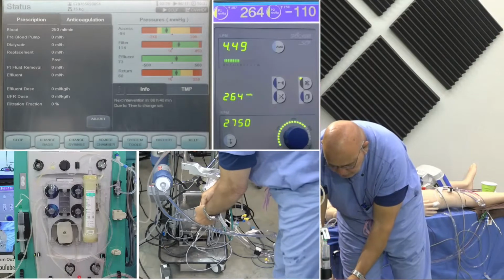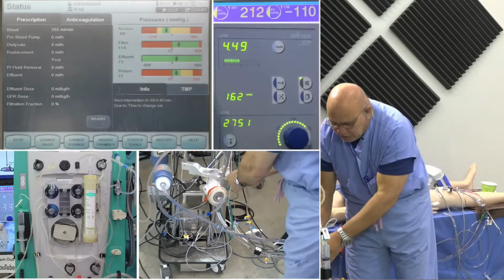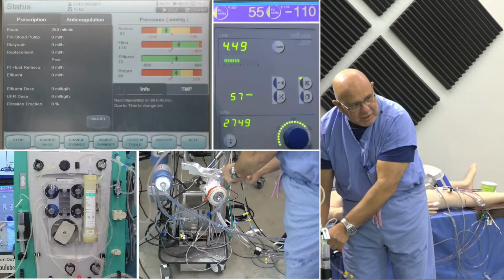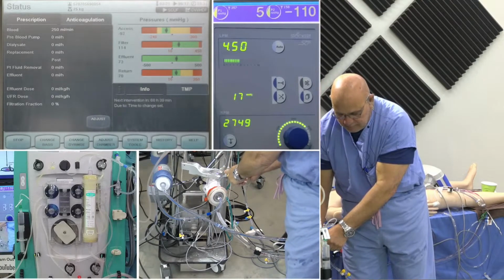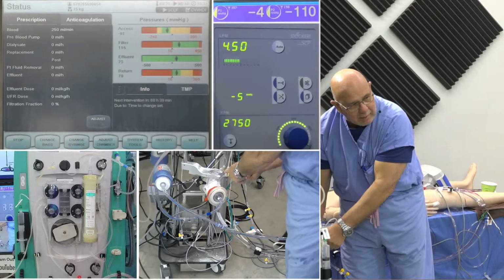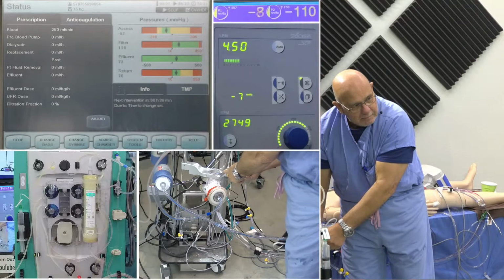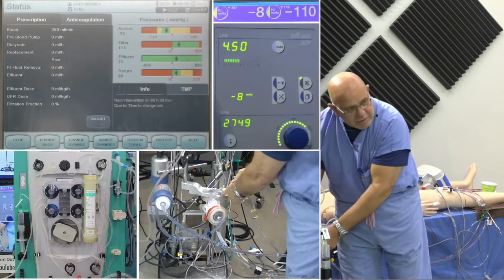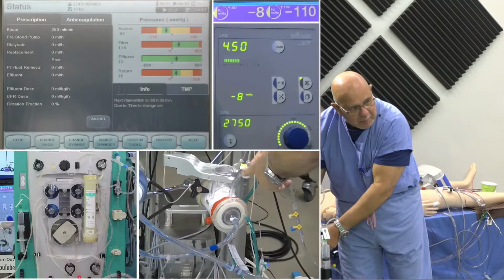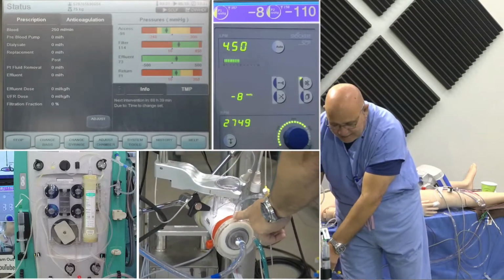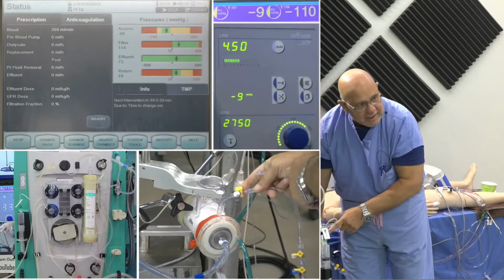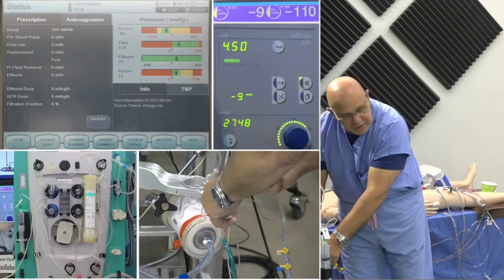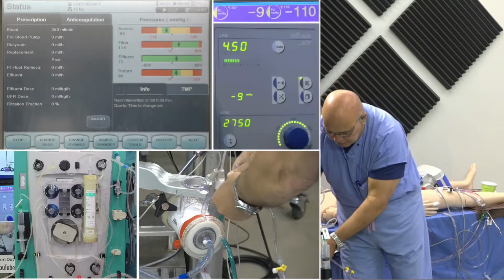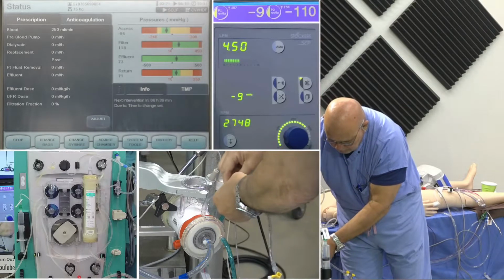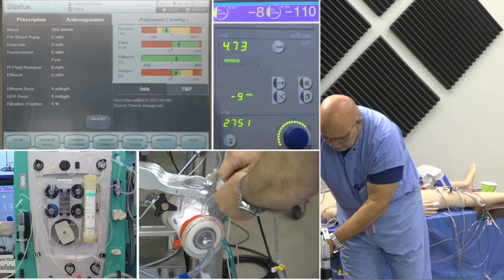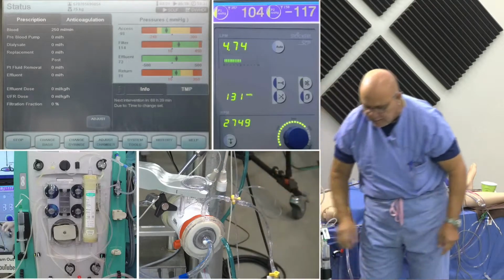And now what I'm going to do is measure the pressure at the top of the oxygenator. Can you focus in on this area, can you? This where my finger is, in the bottom right screen. So at the top of the oxygenator, and every oxygenator has this, especially if you're using it for cardiopulmonary bypass, which is common, you have this line at the top of the oxygenator used for usually de-airing, recirculation. I'm going to measure the pressure here and compare it to those other pressures. Okay, now I have that on, and what do we get?